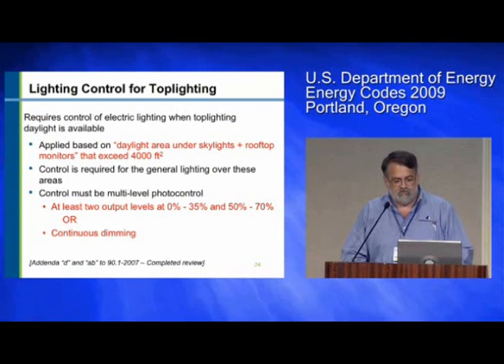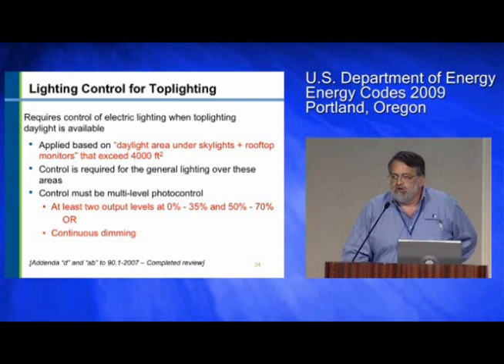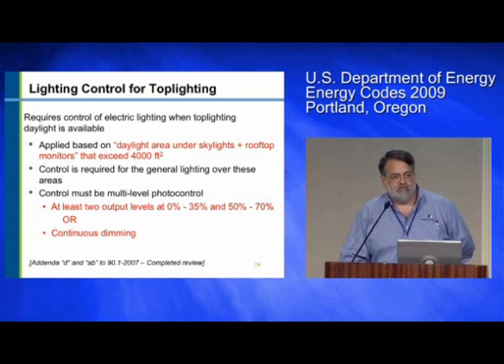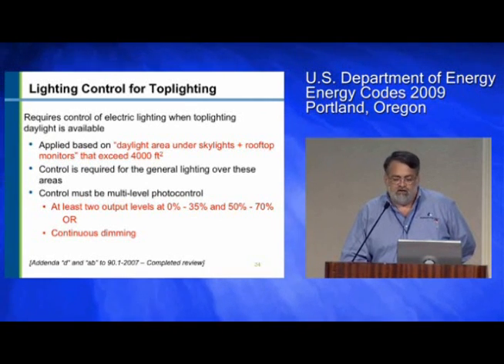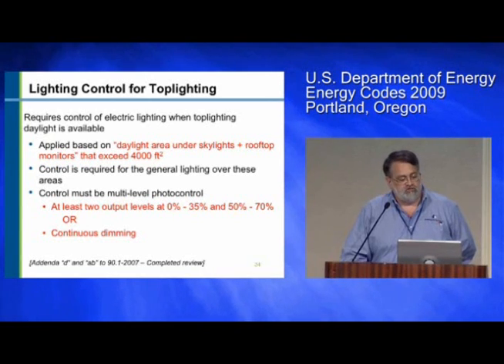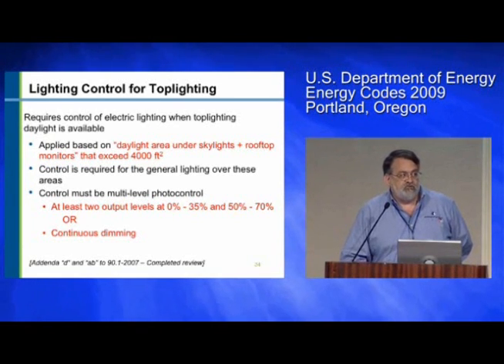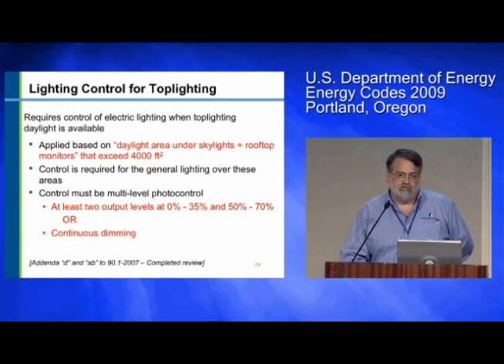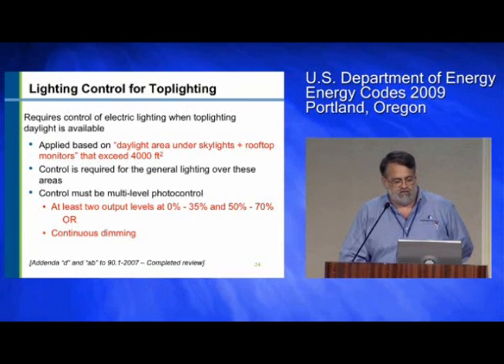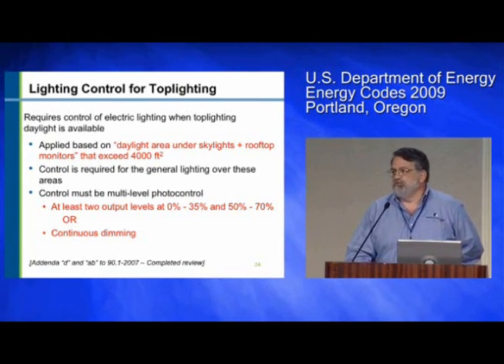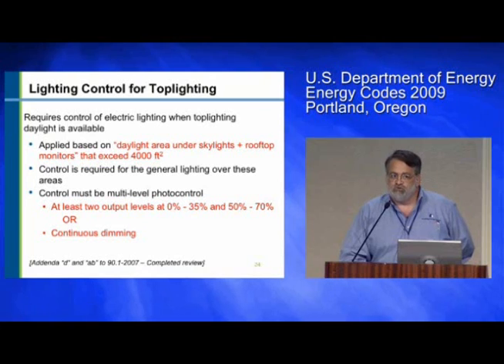Top lighting, in terms of daylight: there is a requirement that if you have skylights, you must control the lighting underneath it if it's a large enough area. It's based on a definition of daylight area under skylights. There's also a definition for rooftop monitors. Essentially, if your space is large enough, in this case exceeding 4,000 square feet for most applications, you have to control the general lighting in that space. And it must be controlled in a certain manner.